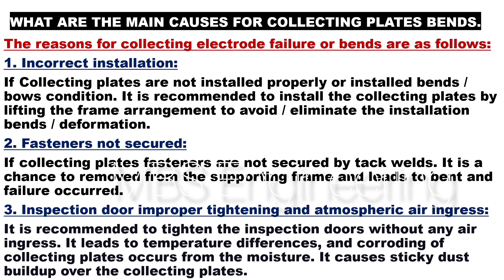One of the main causes of collecting plates bends is improper installation related issues. One of the causes for collecting plates bends is incorrect installation. If collecting plates are not installed properly or installed in bent condition, it is recommended to install the collecting plates by lifting the frame arrangement to avoid and eliminate the installation bends and deformation.